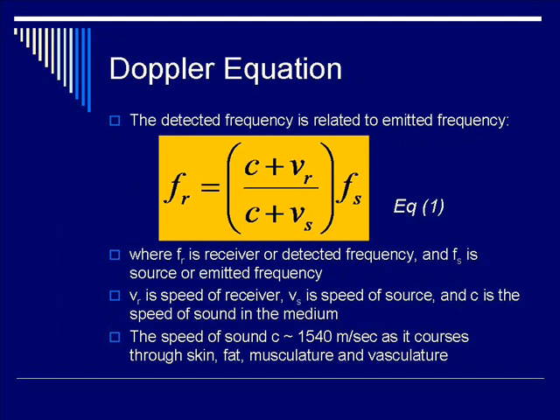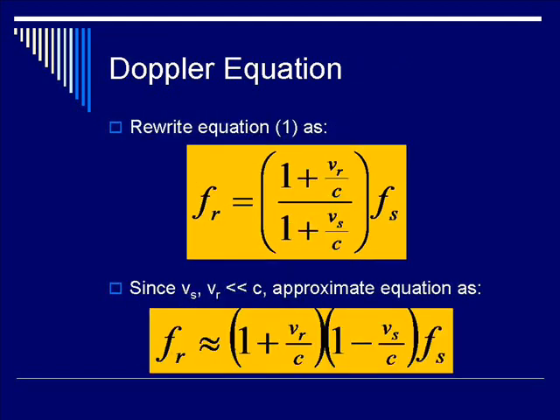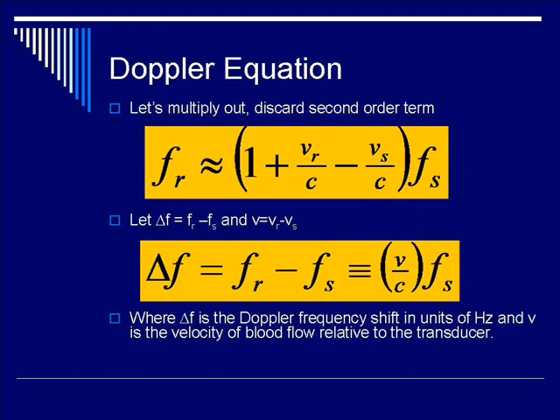Let's construct the Doppler equation from scratch. The characteristic wave equation incorporates Doppler shift, where the frequency of the receiver, F_R, equals a fraction multiplied by the source frequency. V_R is the receiver speed, V_S is the source speed, and C is the speed of sound within the medium — 1540 meters per second for soft tissue. After some manipulation using calculus, the Doppler shift frequency F_D is approximated as: F_D = F_S × (V / C), where V is the velocity and F_S is the source frequency.